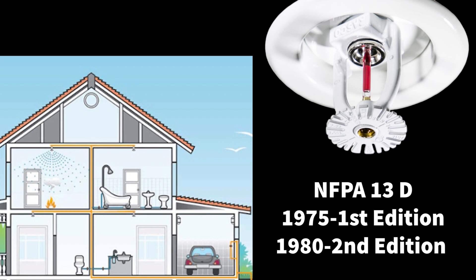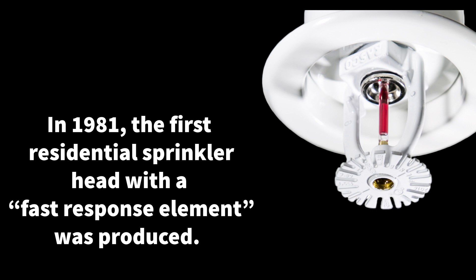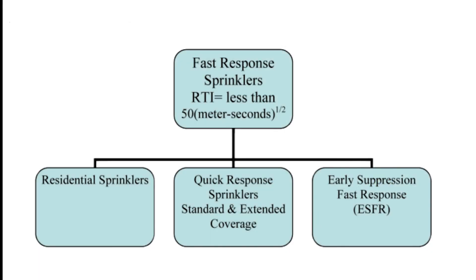The need for fire sprinklers in residential occupancies sparked the innovation for creating a faster responding head — preventing flashover and protecting life safety was the number one goal. The residential sprinkler head was the birth of the fast response element. In 1981, the first residential sprinkler head with a fast response element was produced. The benefits eventually made their way into the commercial head, creating a fast response category with an RTI of less than 50 — which includes the residential sprinkler, quick response standard spray, extended coverage, and the early suppression fast response (ESFR).